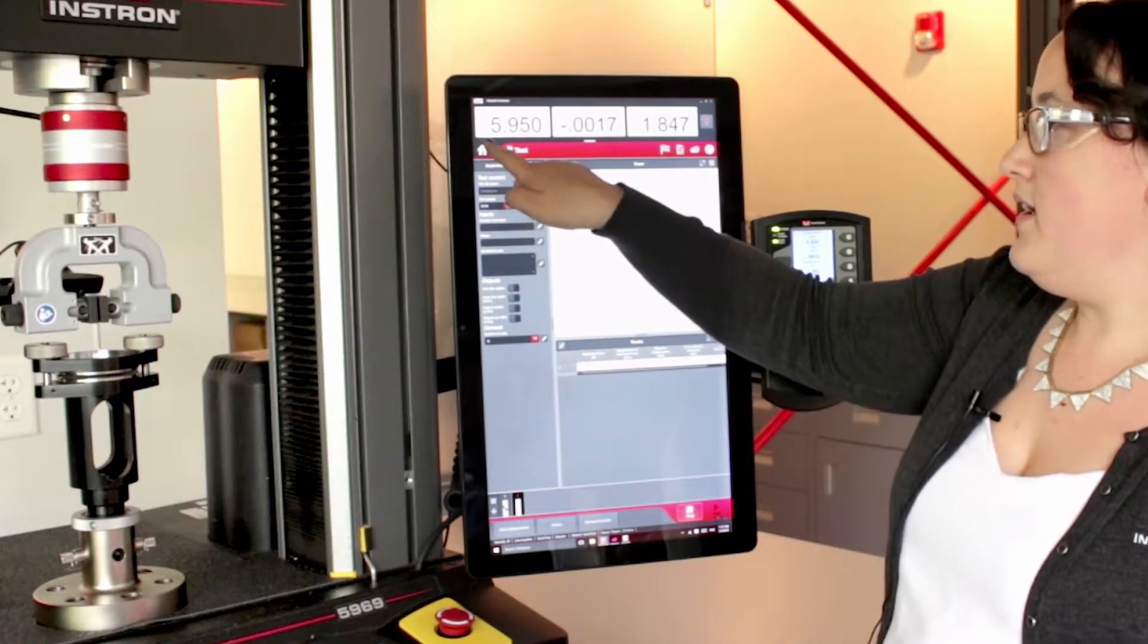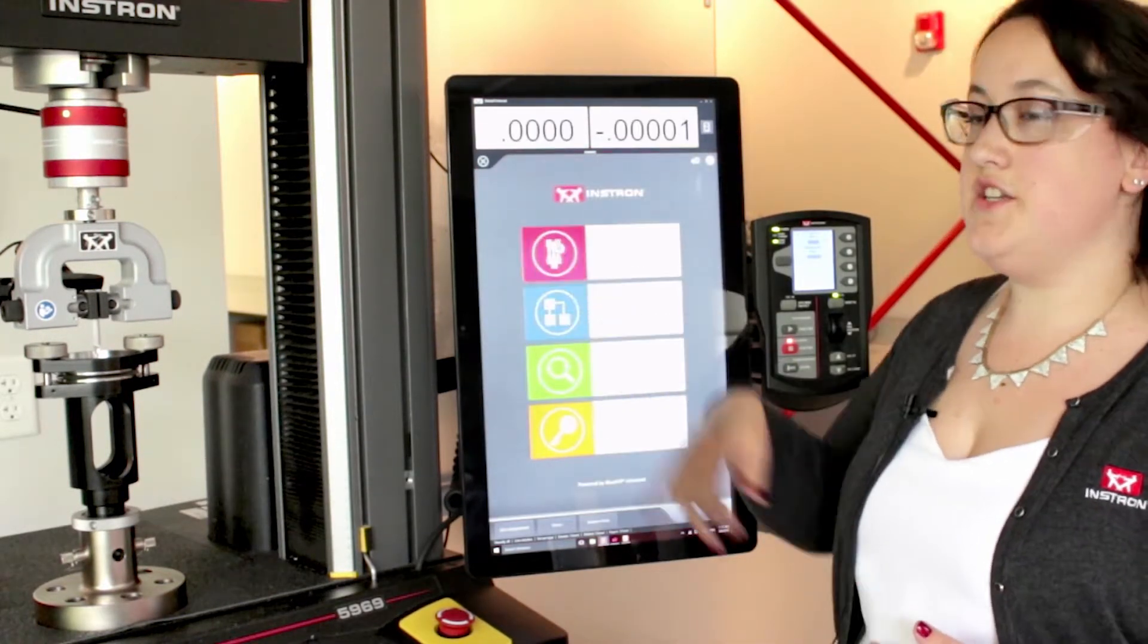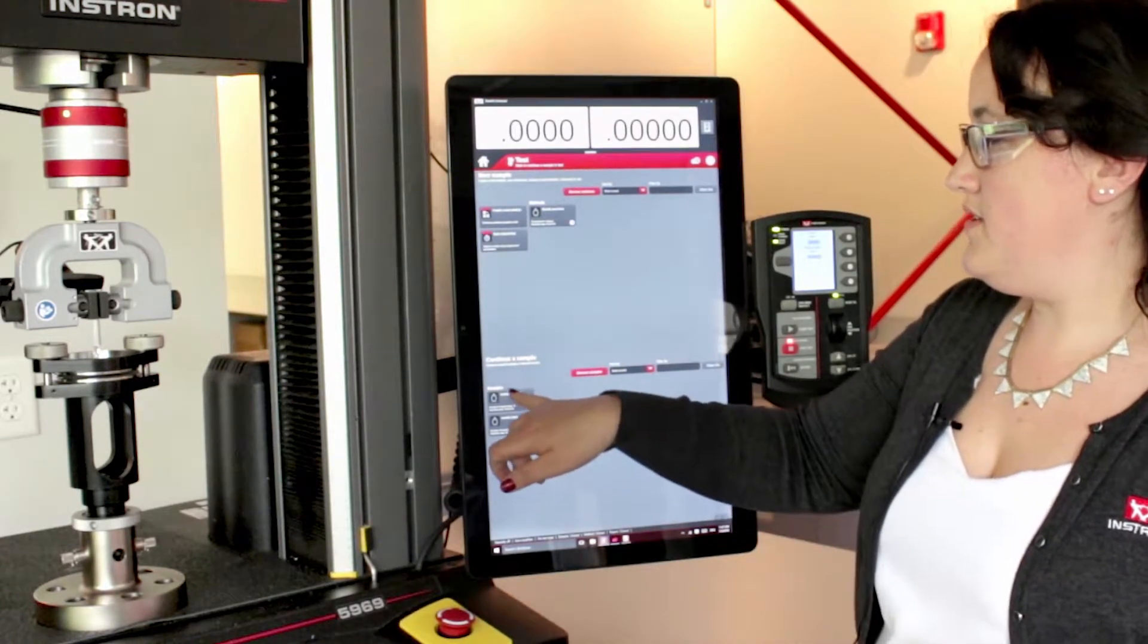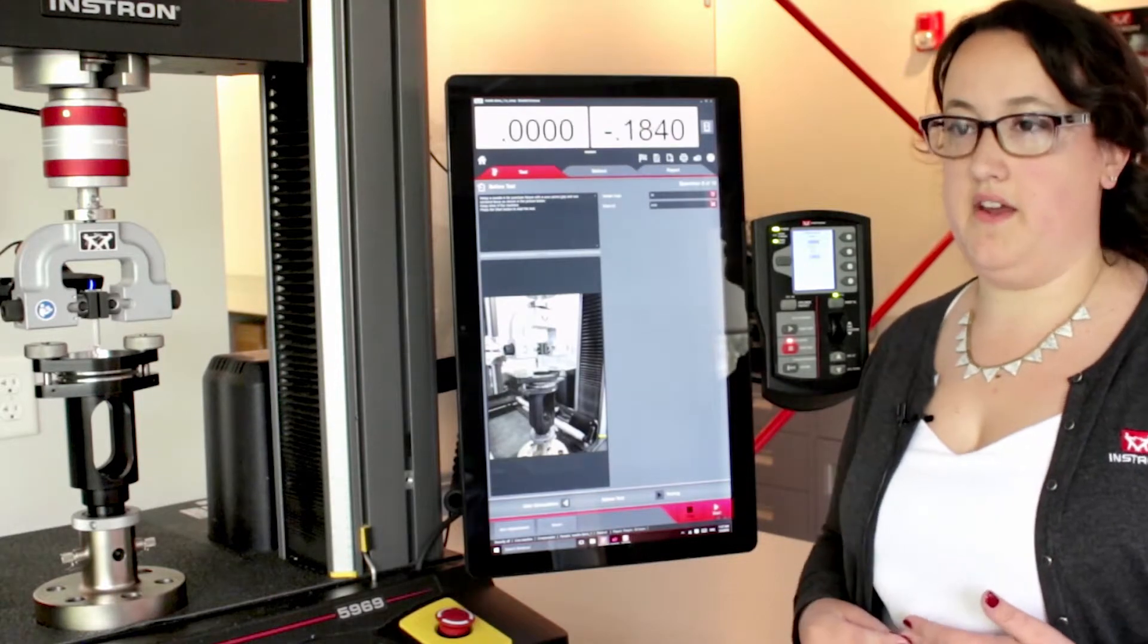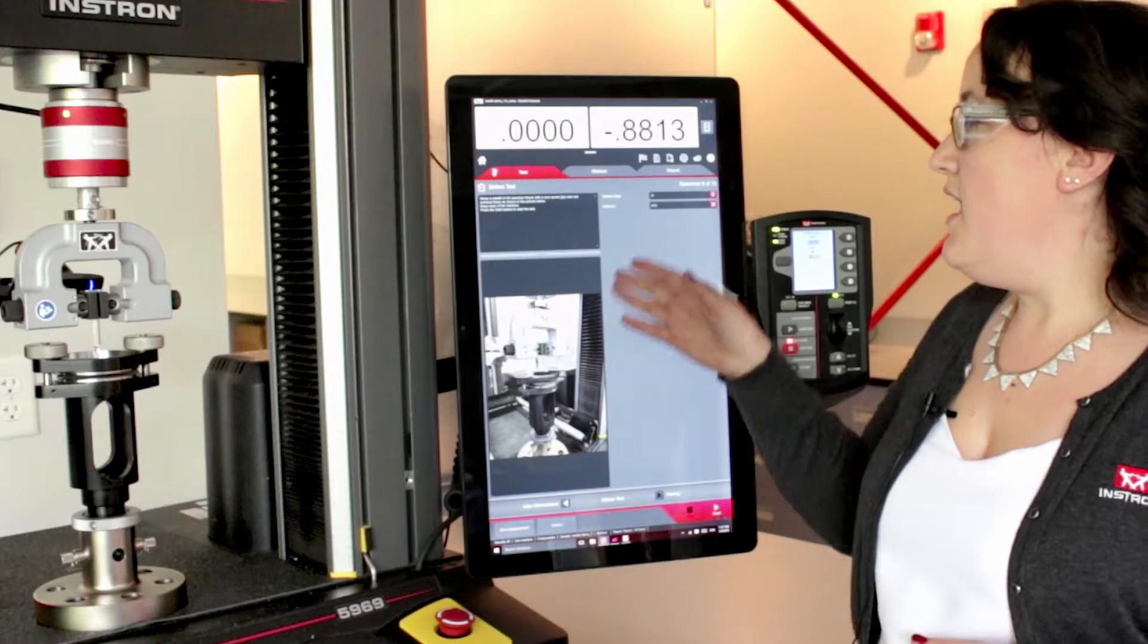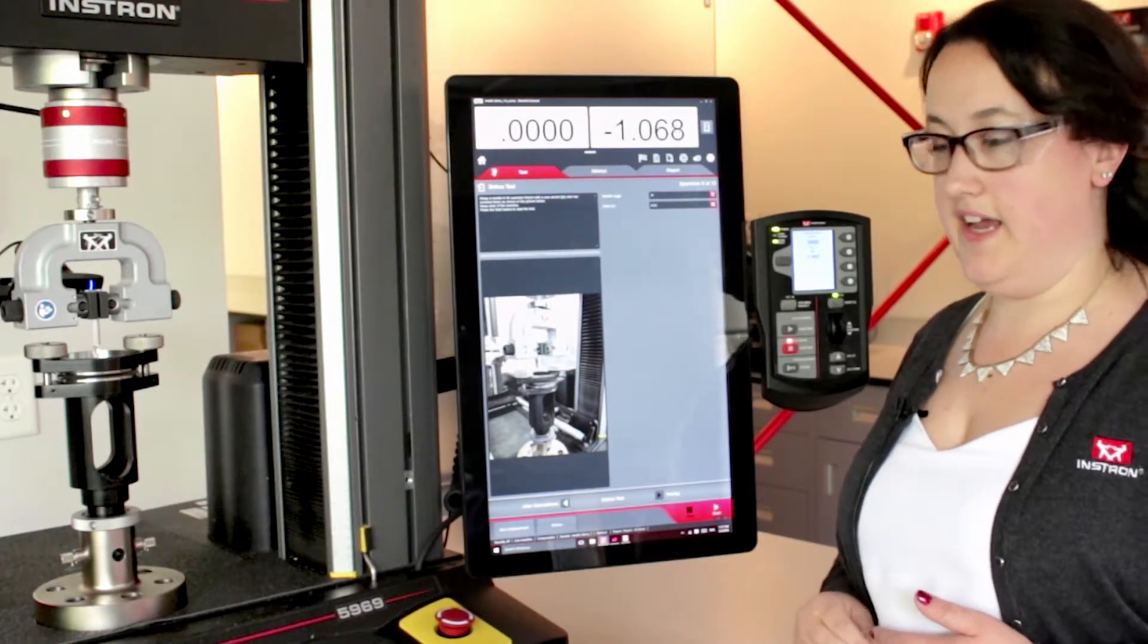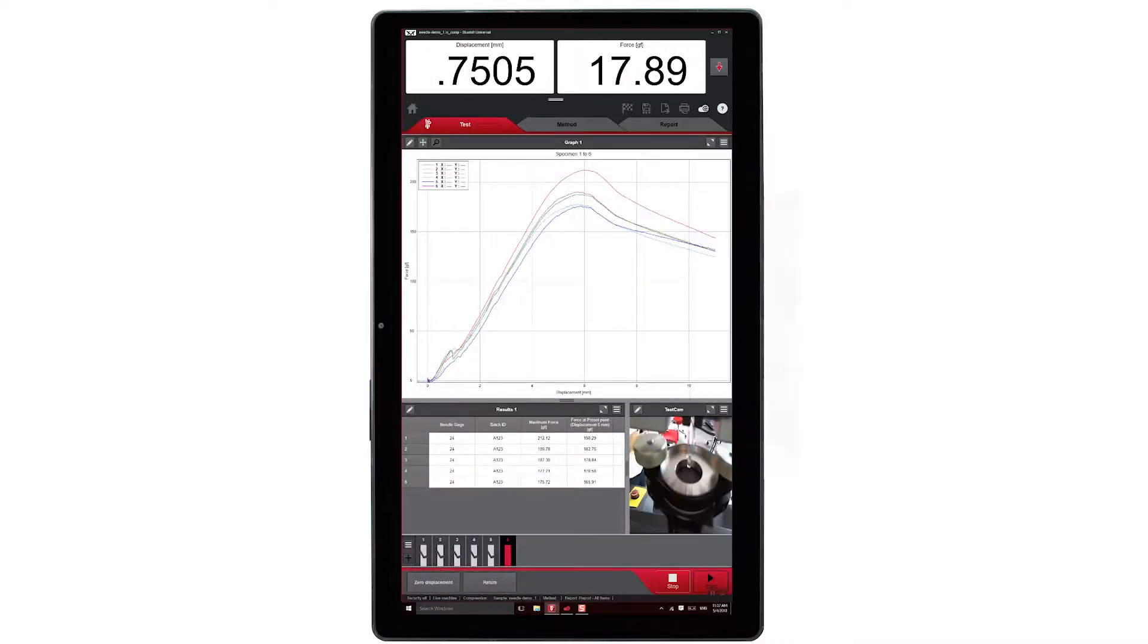When running more complex tests, operators have the choice of continuing specimens previously run, or choosing an existing method file. Here I have a prompted method, which walks operators through setting up for a needle puncture test and inputting simple information such as my needle gauge and my batch ID. Now I hit start and begin my test.